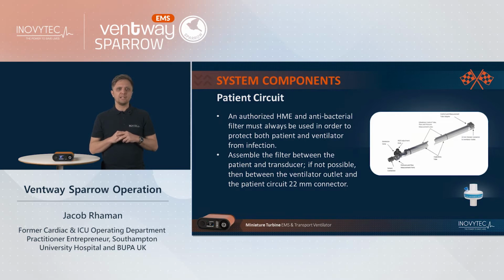An approved HME and antibacterial filter must always be used in order to protect the patient and ventilator from infection. You must assemble the filter between the patient and transducer. If this is not possible, then between the ventilator and the patient circuit 22mm connector. The adult patient circuit is indicated for use for patients weighing over 15 kilograms and is 1.8 meters long. The pediatric circuit is for use for patients between 5 kilograms and 15 kilograms. The Ventway Sparrow is not suitable for patients below 5 kilograms.